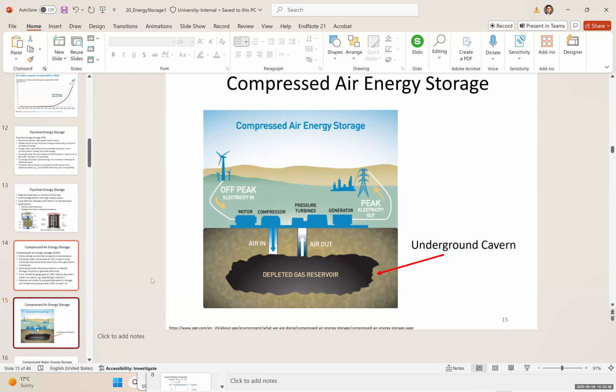One thing to keep in mind for compressed air energy storage is that it has several problems. First, because we're converting electrical to mechanical energy, and then that mechanical energy drives a turbine which converts it back to electrical energy, you have losses in the compressor and generator, especially since these compressors get very hot. Another problem is leakage, since these caverns have cracks and the air may escape. So it's not very efficient.